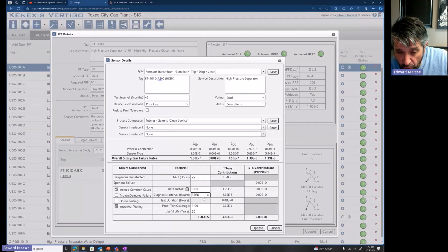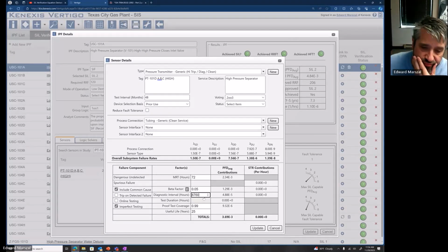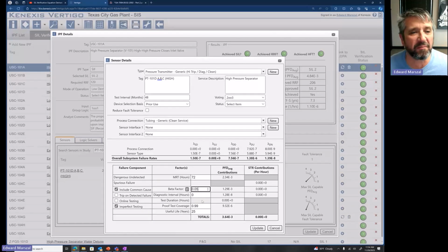So even though one of the 3 transmitters takes a year to get fixed, you still have a 1 out of 2 vote of the other 2 transmitters. And 10 to the minus 4 if you go to 2 years. But I did a bit of a test on this specific item you had there on the screen because I was curious while you were talking about this parameter. Yep. Absolutely. Fun with numbers.